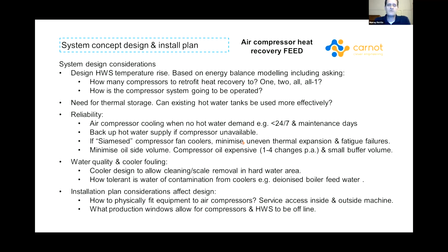Similarly, when you start adding extra pipes and coolers, what's the actual volume of oil that you are going to need to fill those coolers? The oil needs to be changed every now and then, a couple of times a year at least. The separator tank is also your oil reservoir, and that has a finite volume. So if all of a sudden when you start your machine, you put all of that oil into the hoses, you don't have any buffer volume and your machine will eventually overheat. So it's not just a fairly straightforward thing. You need to consider all of those considerations when you're designing the system.